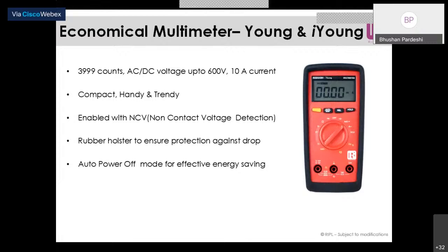Now, basically, what is meant by non-contact voltage detection? As we know, we use testers to check whether a board or line has any supply. In many utility sections, we use bulbs to check whether the line has supply. Non-contact voltage detection eliminates the use of these elements. When you switch the knob to non-contact voltage detection, it has an inbuilt amplifier which detects the EMF induced by the voltage flowing in a circuit, so it will detect whether the circuit has any supply source or not.